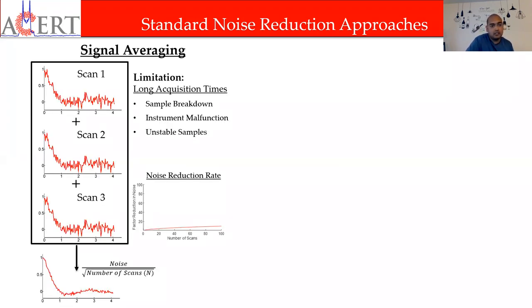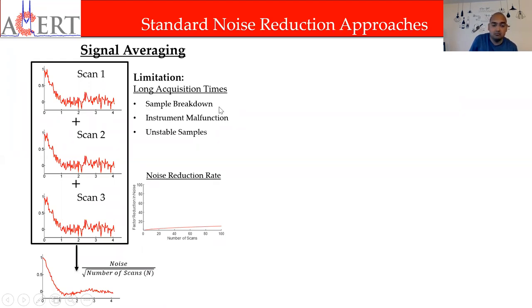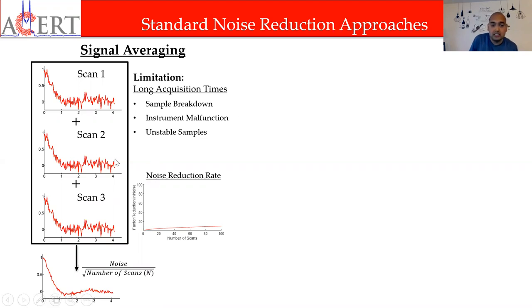What are the traditional approaches to removing noise in ESR? One is signal averaging — you repeat the experiment multiple times and average them to get a better signal. But signal averaging is pretty slow. To get an improvement by a factor of 10, you have to repeat the experiment 100 times — that's by the square root of N. Limitations include sample breakdown, instrument wear, and unstable samples that can't stay there for so long.